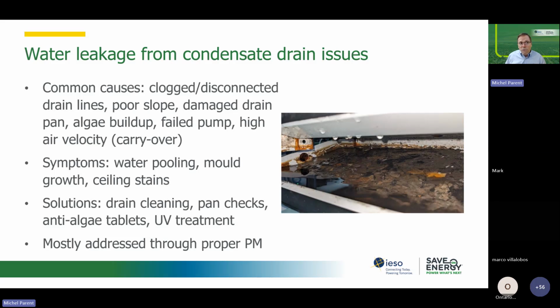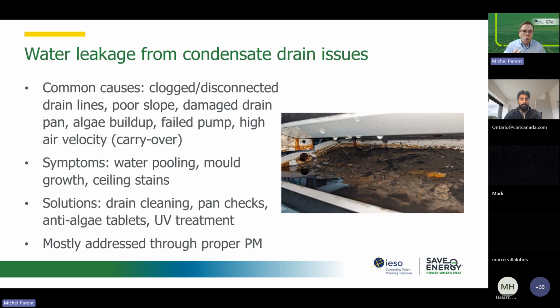A very frequent issue that you definitely need to address in your PM program is water. It says water leakage, but sometimes it's water accumulation. It's water carried over through your system. Anytime you have water sitting in an HVAC system, it is a sanitary issue because you will have mold growth. You can distribute that mold throughout the building. So it has to be a very important point in your PM program to make sure that all the drains are properly cleaned. You may need UV treatment on your cooling coil, and that has nothing to do with virus, by the way.